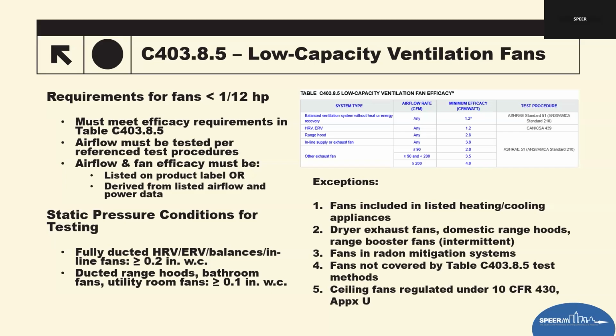These pressures reflect typical installed conditions and ensure the fans are not underrated, are not rated under unrealistic low restrictions, such as poorly installed ducts can dramatically change that pressure in that inches of water column. So to test it and verify and validate CFM, this is the test pressure that you're looking for. There are exceptions. There's 5. One is part of the listed HVAC appliance.